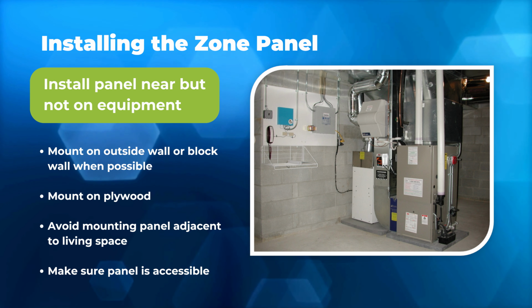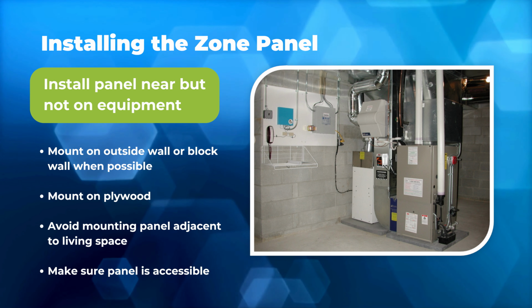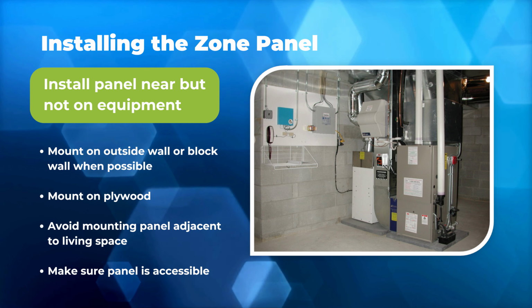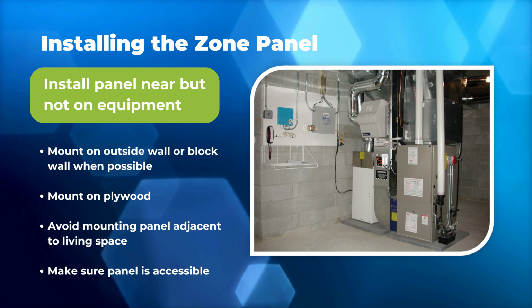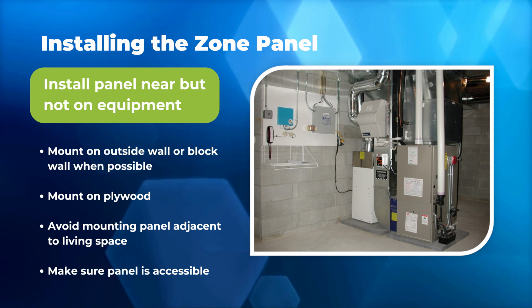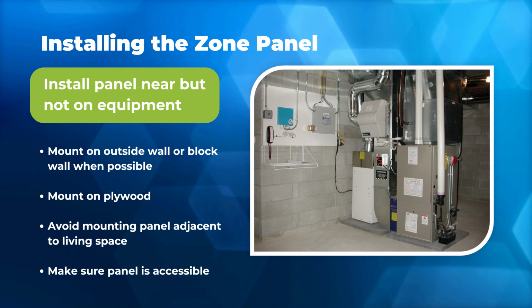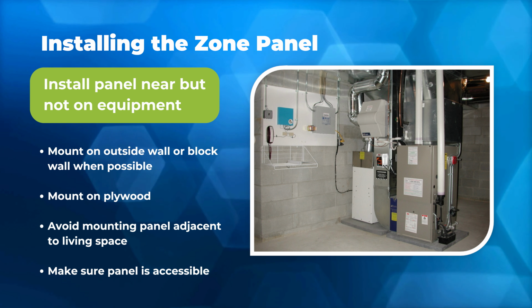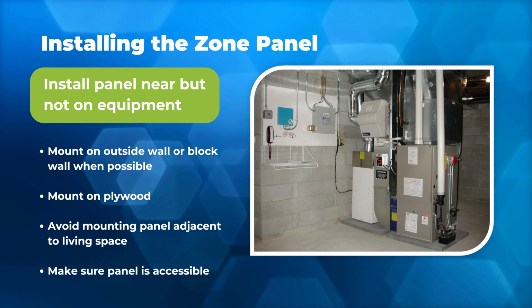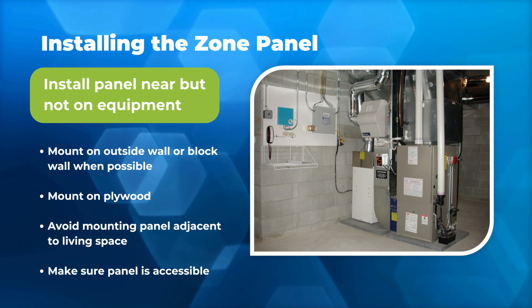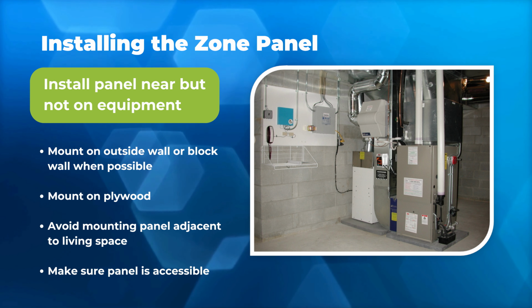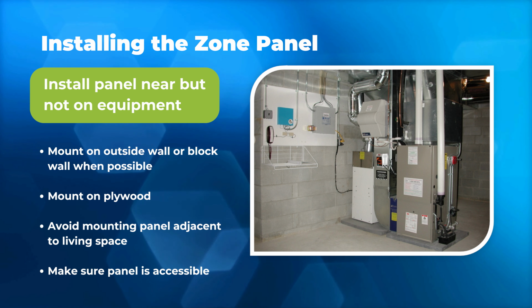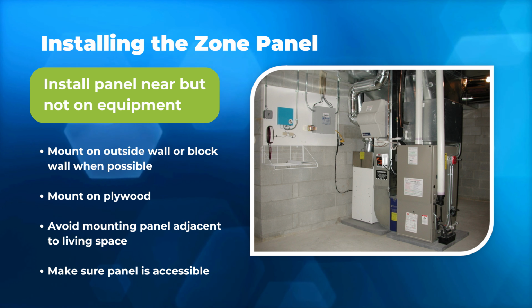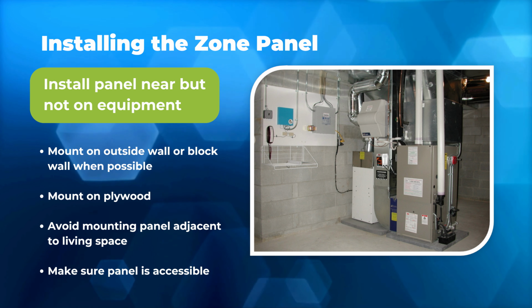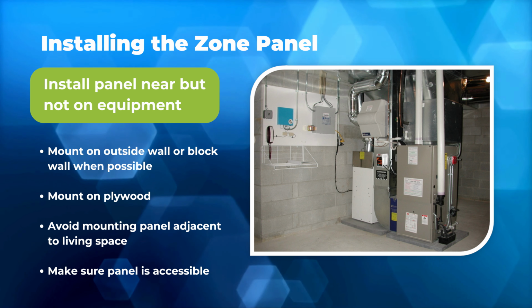You always want to be aware of where you're mounting it as well. You're going to want to stay away from an adjacent living space. So if they've got a bedroom in the basement or something like that, you're not going to want to put it on the opposing side of that wall because they will get some echoing. And you never want to mount it to the equipment or the return duct. The reason being is because of that pump vibration. If you mount it on the return, you're going to hear that echo throughout the whole house because it's going to vibrate that sheet metal and you're going to get that sound going throughout the entire home.